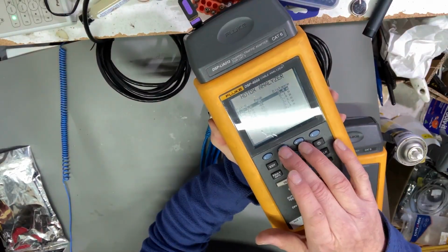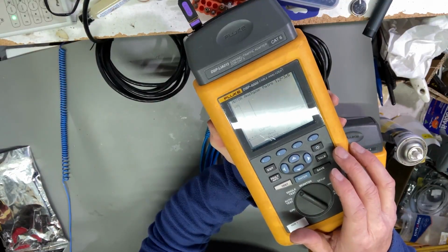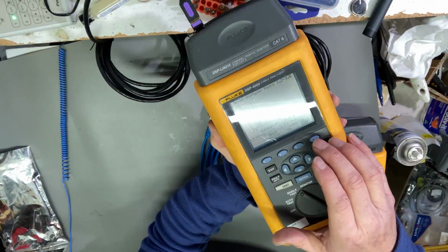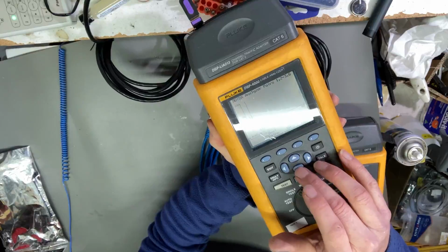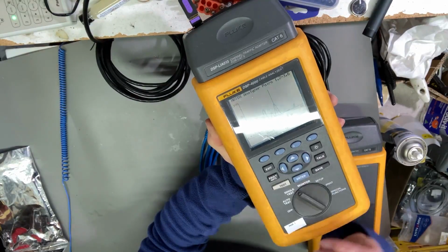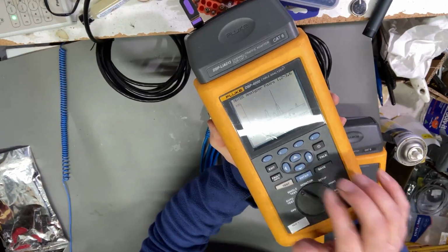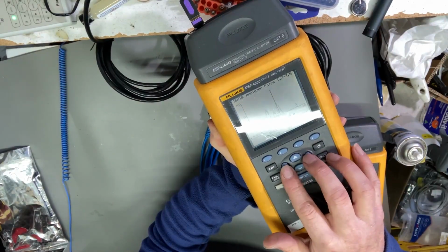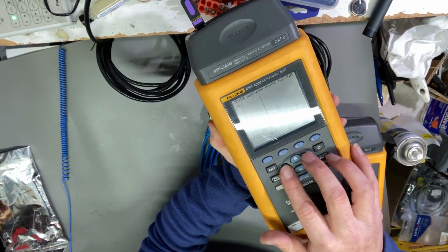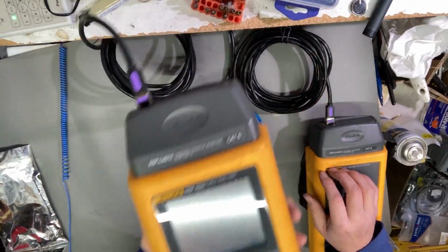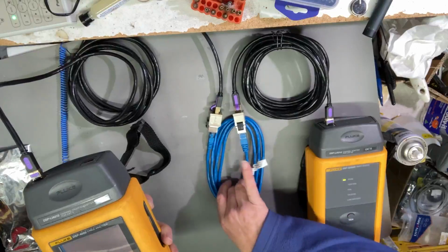Right, now if we view the plots on those, if I zoom in here, let's go adjust scale. Right, so what we've got there is a lot of reflections. I'm thinking that these two here, that's at 3 meters, so that's the coupler. So that bumpy bit there, what I've got here is 2 3-meter cables at each end, which are okay.